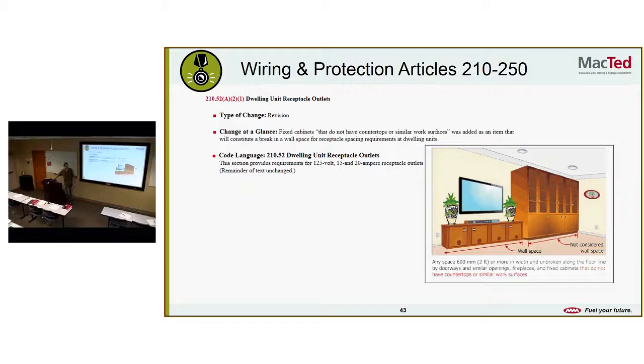Dwelling unit receptacle outlets. So this applies to your house. Revision: fixed cabinets that do not have countertops or similar work surfaces was added as an item that will constitute a break in wall space for receptacle spacing requirements at dwelling units. This section provides requirements for 125 volt, 15 and 20 amp receptacle outlets. If you've never gone through this, you're supposed to have an outlet within 6 feet of each other. The idea is you shouldn't have to run extension cords along paths of travel. And so now they're saying this counts as a wall space.